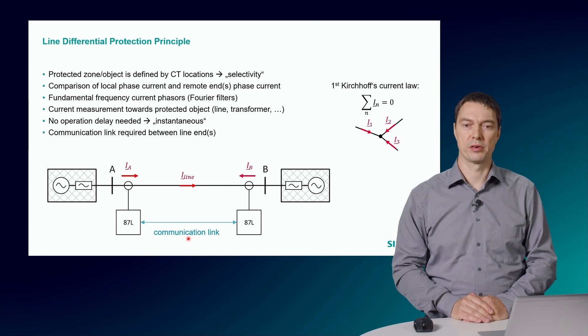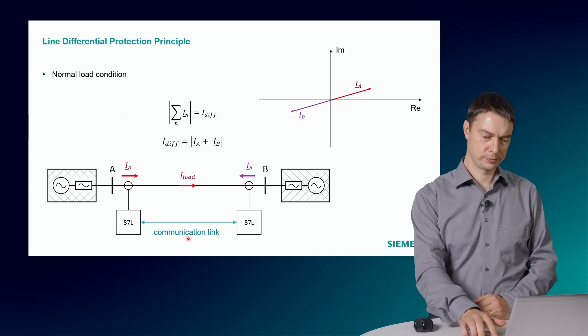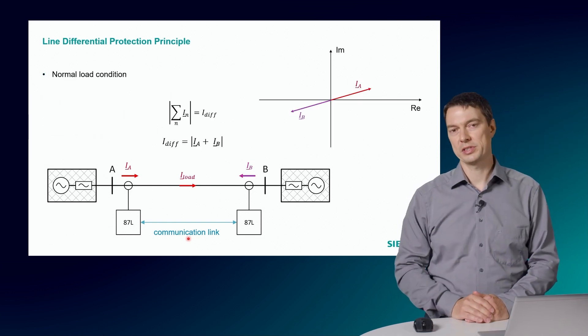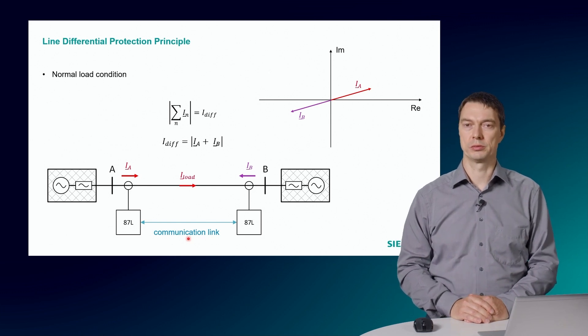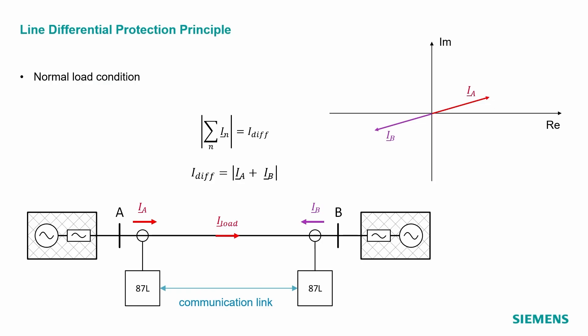Let's have a look what happens if we have a current flowing at the line. In the first example, we have the normal load condition, which is a load current flowing at the ideal line, shown here. And we look at the phasor diagram on the top right with the imaginary part and the real part of the phasors, which are measured by the protection relays. The current IA is measured by the relay in A and the current IB is a current measured in the relay B. This is of the opposite direction because the load flows through the line.